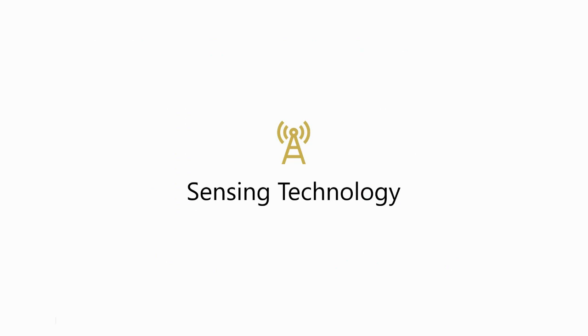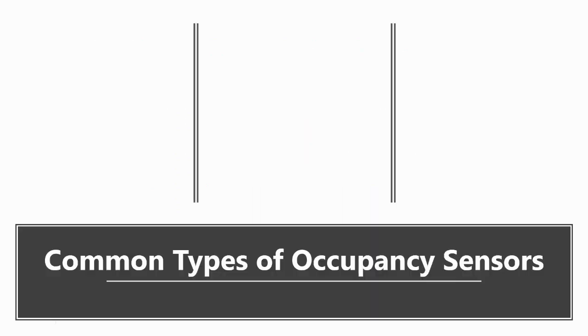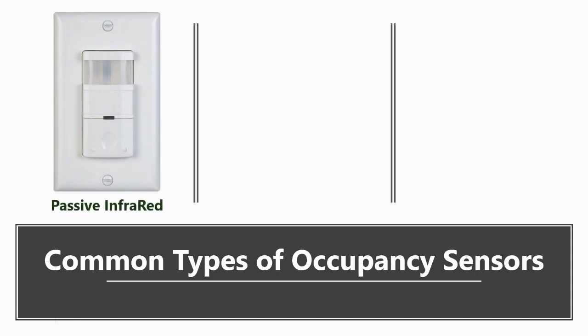Now let's review the most common technologies for sensors. There are three types most often used in commercial buildings. The first is passive infrared. Passive infrared sensors react to the movement of heat emitted by people in motion. They detect motion within a coverage area that requires a line of sight, so they cannot see occupants behind obstacles such as furniture or even glass.